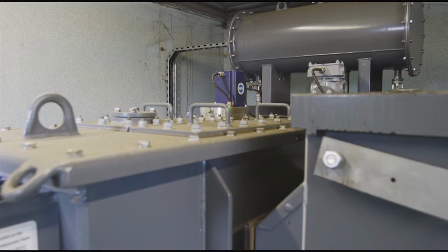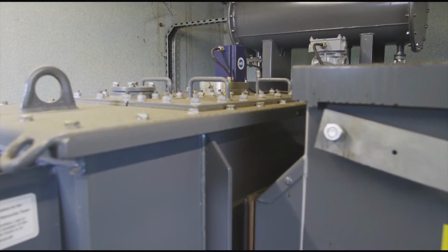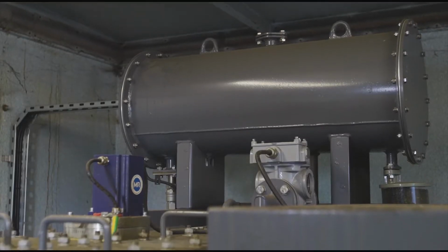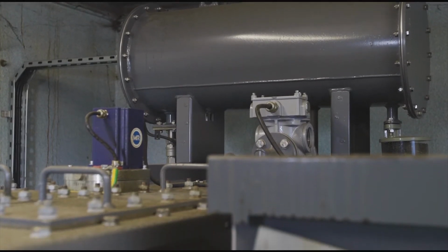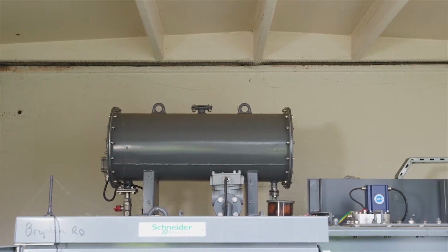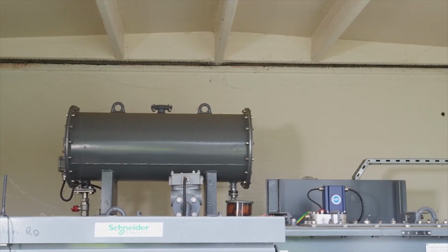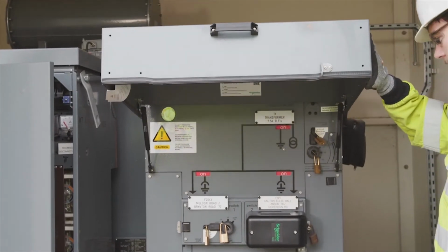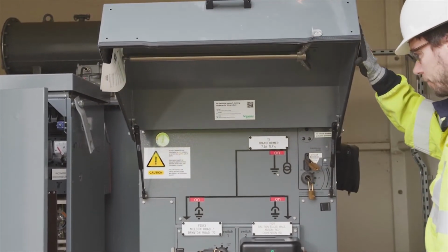Technically, Smart Street is about delivering 180 on-load tap changing transformers into our distribution substations. These are a mix of 11,000 and 6,600 volt transformers of mixed ratings, all cable connected. They'll control the LV voltage by up to 20% around the nominal tap position, compared to standard transformers which only allow 10% control. These tap changers will tap on load, so we control on a regular basis what the output voltage for the LV network is.